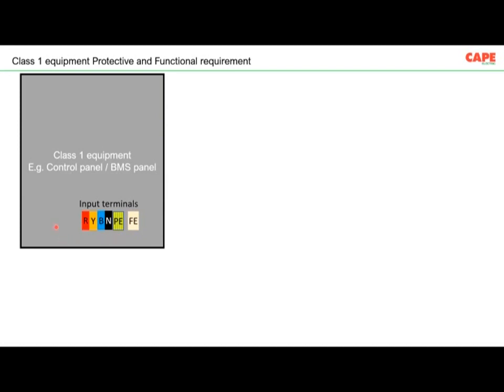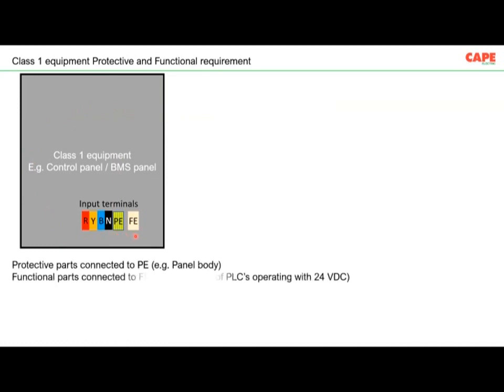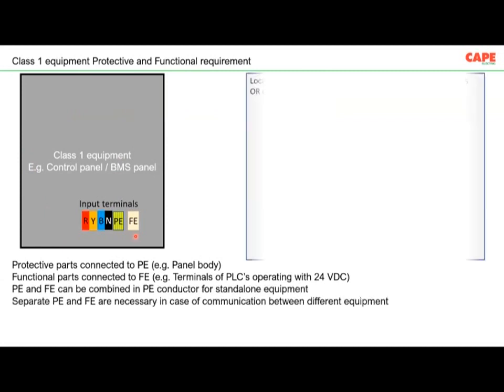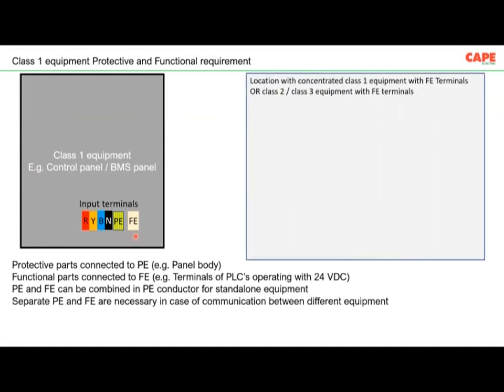Basically, a class 1 electrical equipment requiring functional PE and FE looks like this. It will have three-phase and neutral terminals, a protective earth terminal, and a functional earthing terminal. Now, the examples I have mentioned here. Now, let us see how you make earthing in a control room, for example.